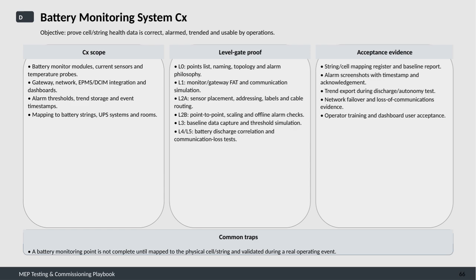For acceptance evidence, we collect essential documentation and proof points. This includes a string and cell mapping register along with a baseline report, alarm screenshots complete with timestamps and operator acknowledgments, and exported trend data from discharge or autonomy tests. We also need to demonstrate network failover capabilities and provide evidence of loss of communications handling. Additionally, operator training completion and user acceptance of the dashboard are critical milestones.